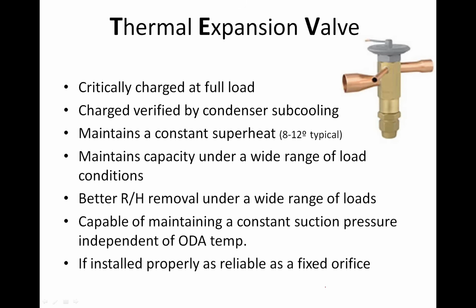The beauty of a TXV is it maintains capacity under a wide range of load conditions. So it's always going to try and maintain the exact same level of refrigerant in the evaporator all the time. And what's interesting is that if the refrigerant level in the evaporator never changes, neither does the condenser. So when you think about how a TXV system is charged, when the manufacturer calls for 10 degrees of subcooling, it's not 10 degrees of subcooling on a mild day and less on a hot day. It's 10 degrees all the time because the TXV's job is to maintain superheat.